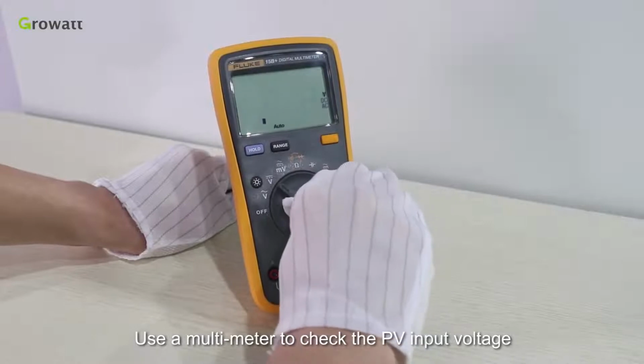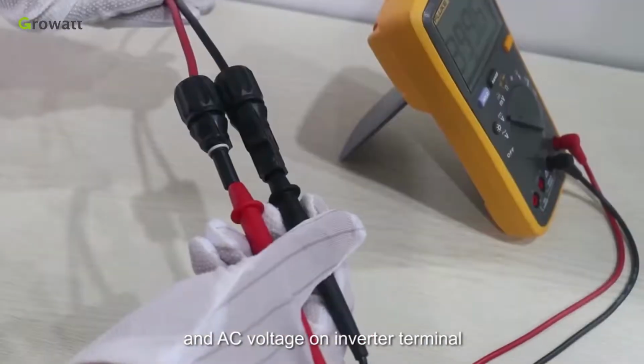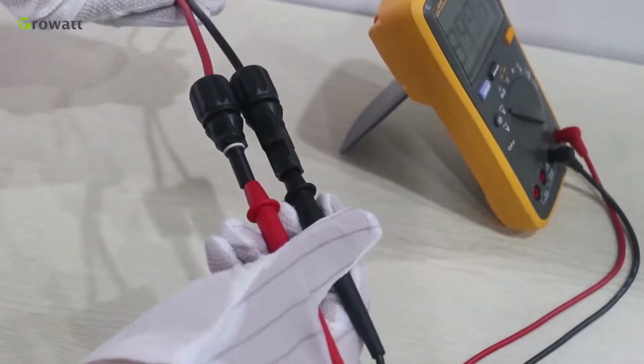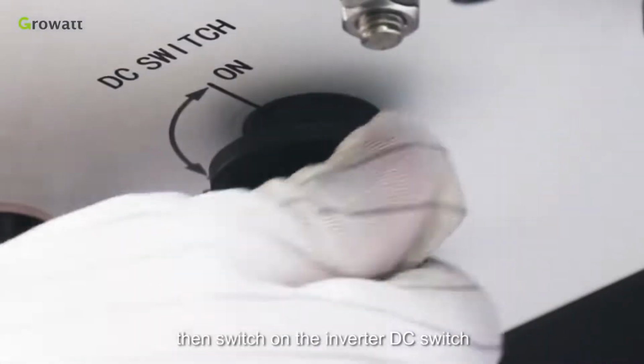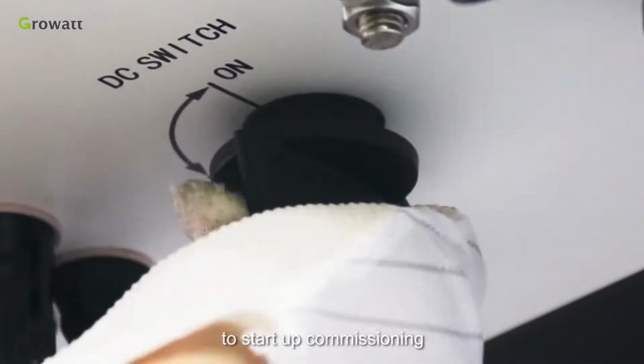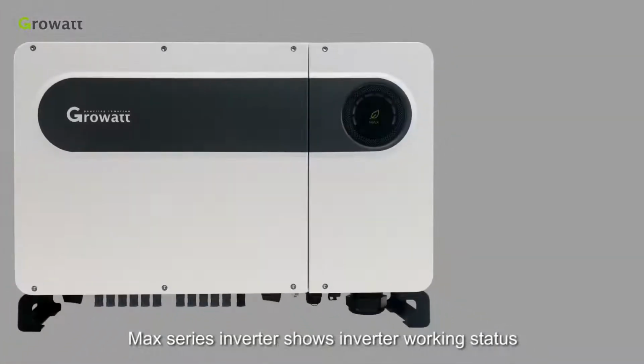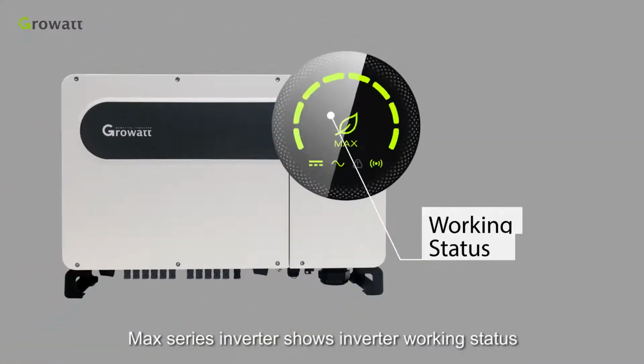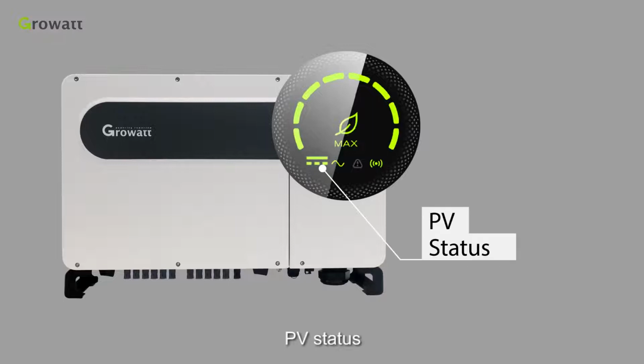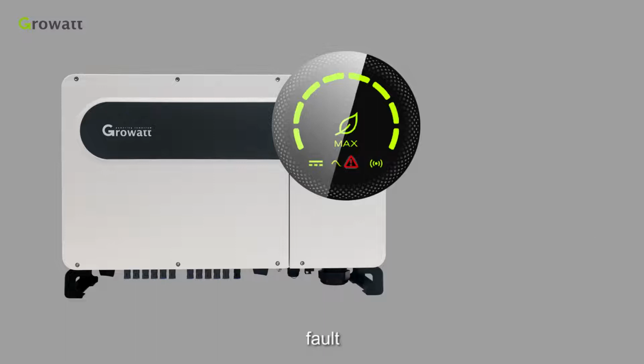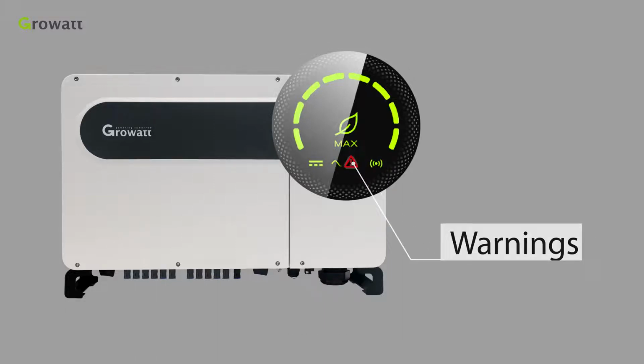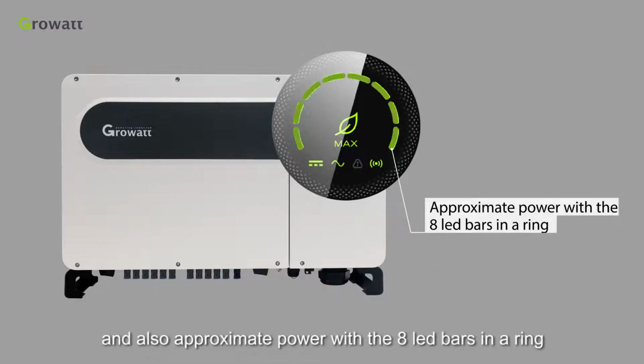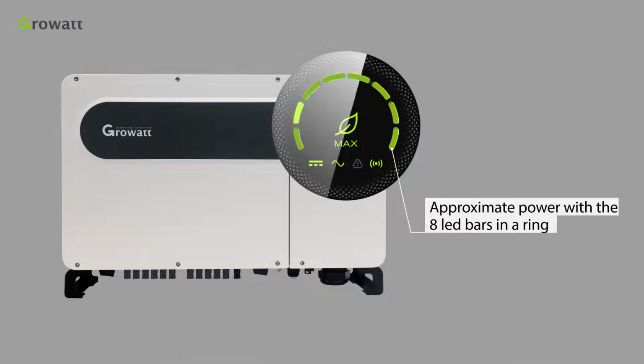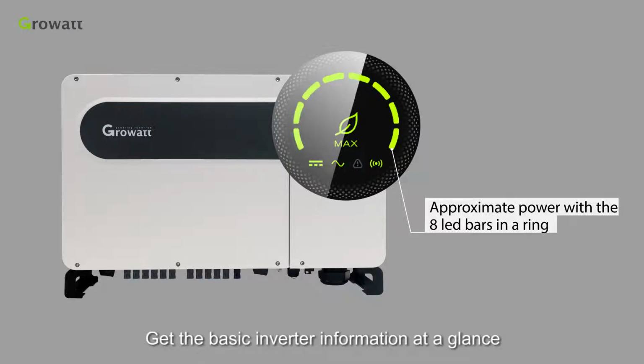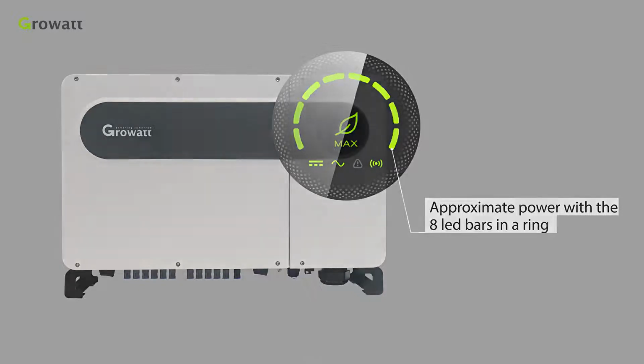Use a multimeter to check the PV input voltage and AC voltage on the inverter terminal. Make sure they are correct, then switch on the inverter DC switch to start up commissioning. The MAX series inverter shows inverter working status, PV status, AC status, communication status, faults, warnings, and also approximate power with 8 LED bars in a ring. Get the basic inverter information at a glance, quick and easy.